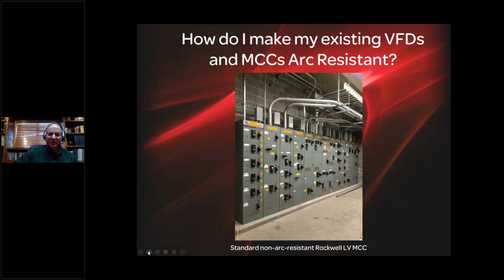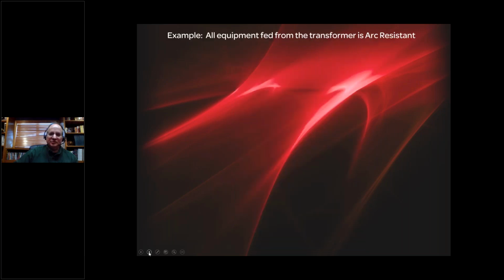So when we look at an existing installation, and this was an existing installation that was subsequently converted, this is a standard non-arc resistant Rockwell low voltage motor control center. You can see in that MCC right in the middle, there are a couple of variable frequency drives sitting there as well inside the motor control center. How do we make VFDs and MCCs arc resistant?